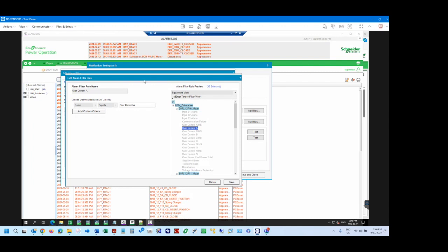And that's what I liked about the Designer level at the meter function. Based on my experience, I could do all kinds of functions on analog values to create another alarm as a result. Like, I could add these two values, B and C overcurrents, put some other type of attribute to it as well, and make this long formulaic alarm requirement all at the meter level. Yeah, lots of condition-based type alarms.